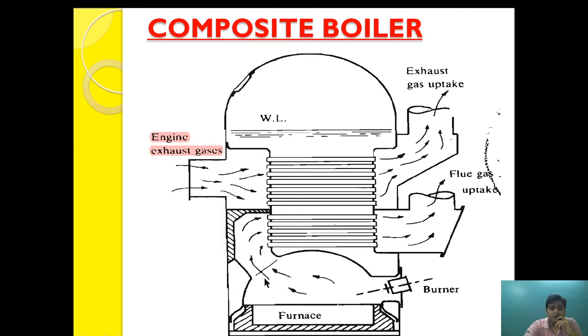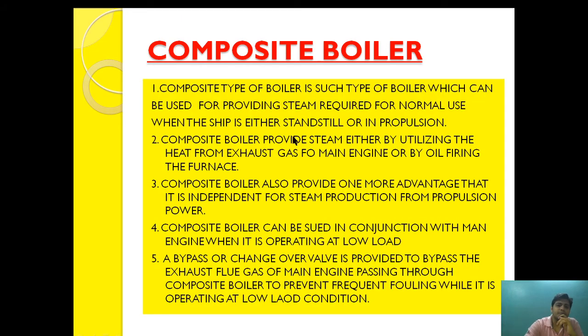The importance of the composite boiler is that it is independent of each system — the engine exhaust gas system is not dependent on the furnace, and the furnace system is not dependent on the engine exhaust. Both work independently for steam generation. Furthermore, if the engine is running at slow, dead slow, or half-ahead speed, the oil-fired boiler can provide additional heat to supplement steam generation and meet the ship's requirements.